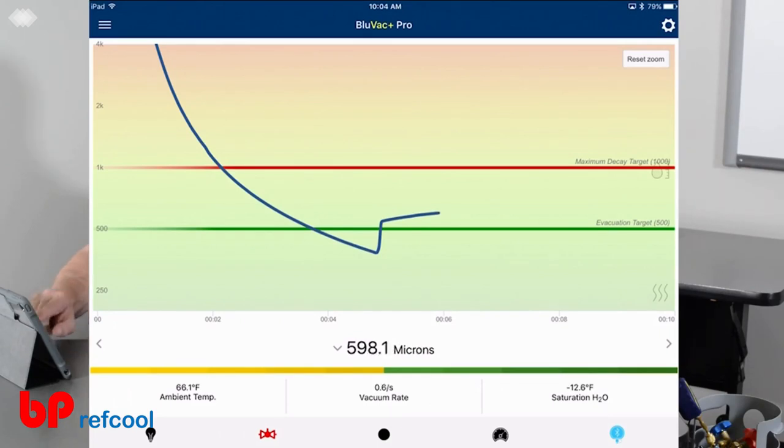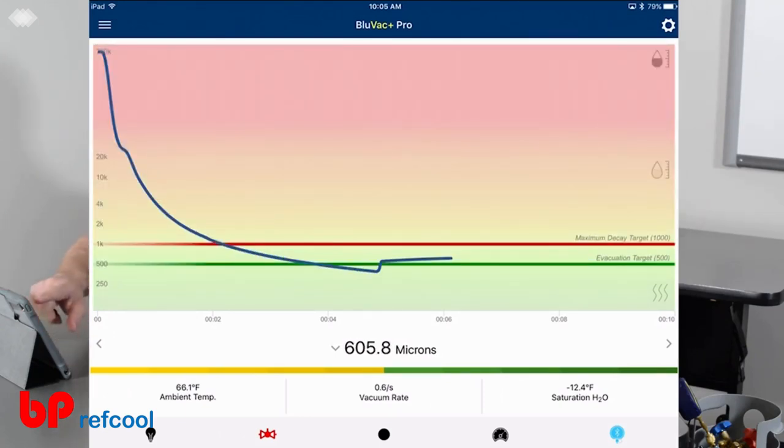You can see this curve here, where we isolated it, and where it's slowly approaching the 1000 microns. It's going to hold that below our decay time. In one minute, there's no way it's going to hit this 1000 micron target. Go ahead here, we'll go back, and let's take a look at our report.